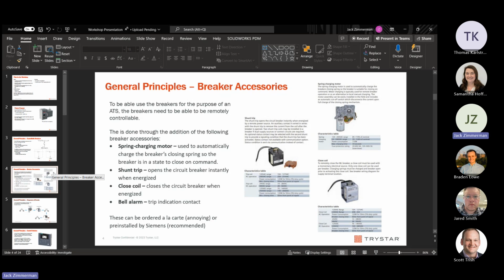With the Siemens breakers, the WL or WA, these are the only acceptable items we can use because these are accessories for the Siemens breakers. So there's two ways we can do it. We can order them a la carte - order all these parts and put them in the breaker, which is annoying, like we spent three days putting all the components in for this job - or you can have them pre-installed by Siemens. Siemens will actually take the spec you need for their breaker and include all these options in it and just give it to us like that.